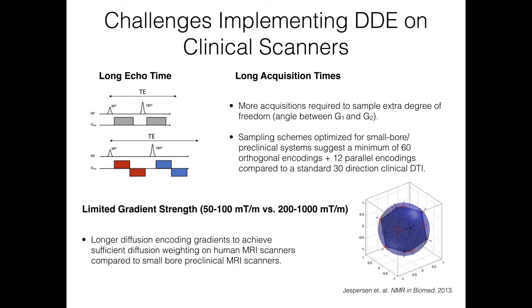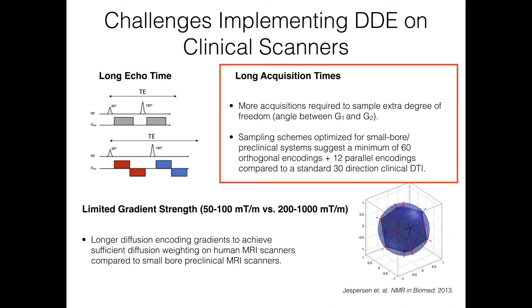There are clear challenges in implementing multiple diffusion encodings on clinical scanners. Diffusion imaging is already SNR-starved, since contrast is based on signal attenuation and gradient play-out takes significant time. Adding two pairs of gradients can really push the echo time out. The initial sampling schemes required quite a few acquisitions, and clinical scanners have much more limited gradient strength compared to preclinical scanners.